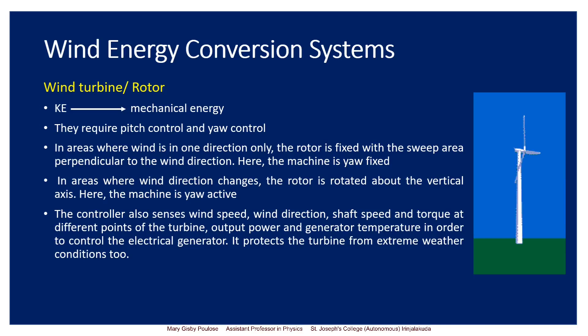In the rotor or wind turbine we also have control mechanisms that check the rotation of the rotor. The controller senses wind speed, wind direction, shaft speed and torque at different points of the turbine, the output power, and the generator temperature, in order to control the electrical generator. All these parameters — wind speed, wind direction, shaft speed, and torque — are continuously changing. The power generated in the generator will differ at different times and the generator might overheat. So a controller is used to sense all these parameters and it also protects the turbine from extreme weather conditions.